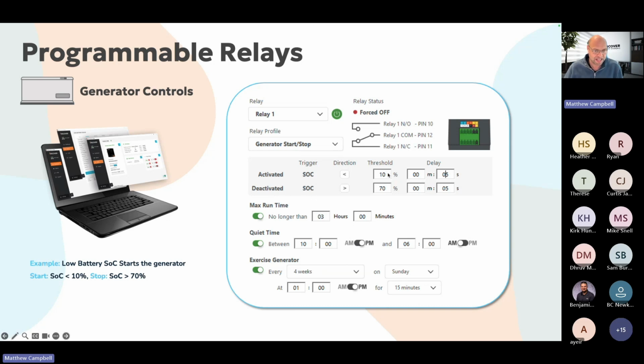You can set on SOC a percentage, and then with a delay. My recommendation to most people is set your delay to 5 seconds. These all come zeroed out as a default. I would do 5 seconds, because if you've run a surge and it dips below 10% just briefly, you don't necessarily want the generator to start right away. So give it a bit of a delay on the activation, and you can also do that on the deactivation as well. In this example, it'll trigger at 10% SOC and it'll deactivate at 70% SOC.